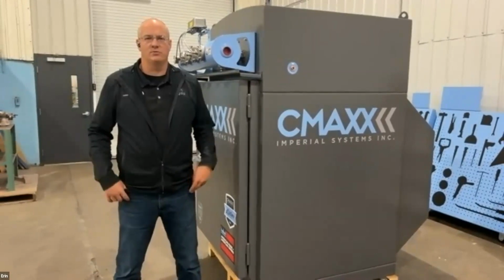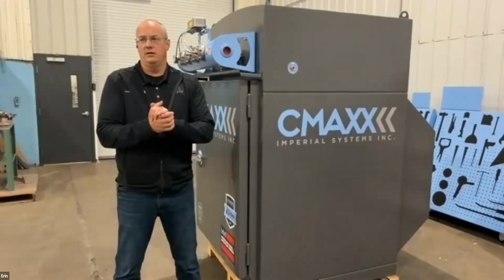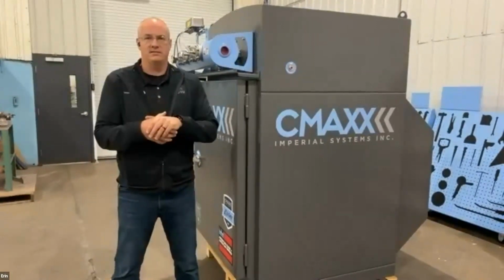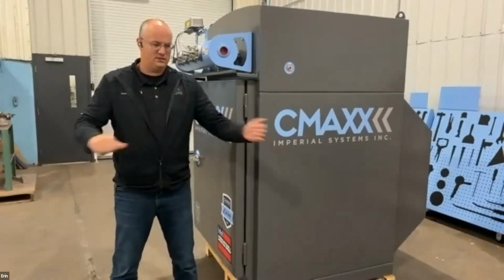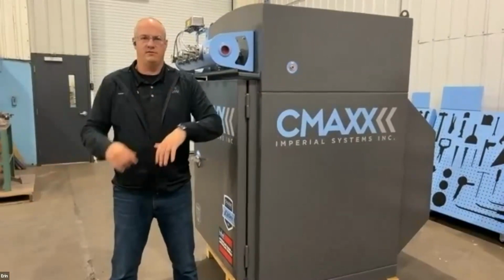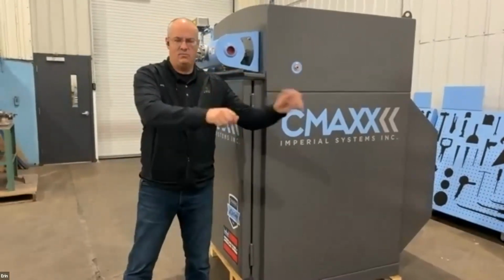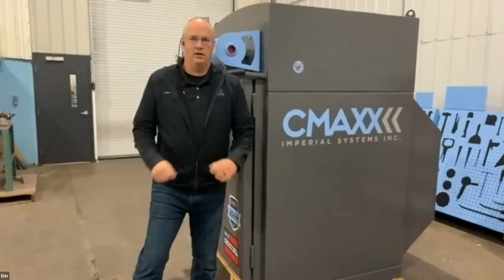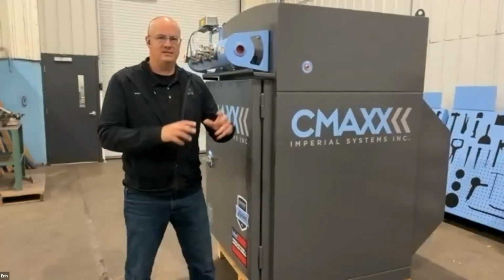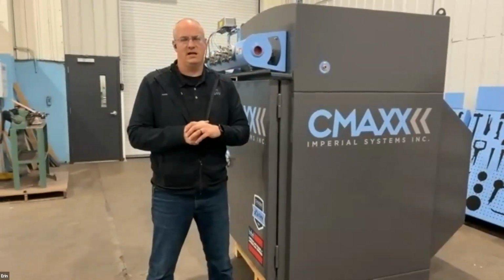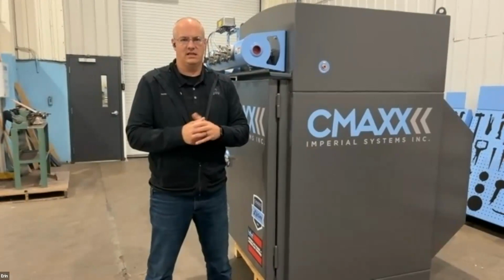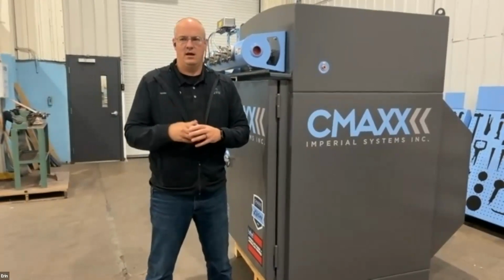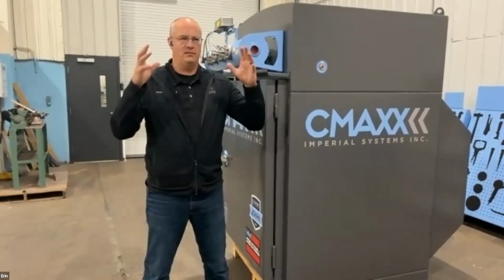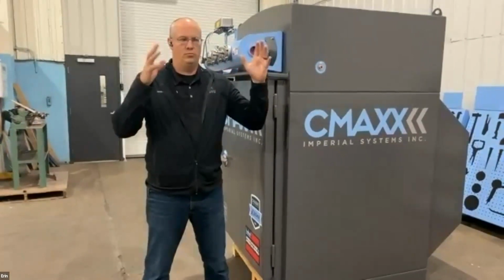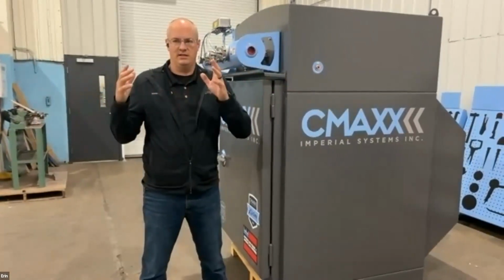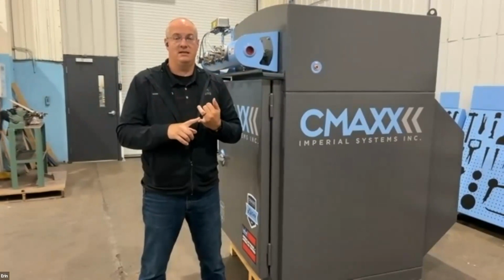A lot of the times when I'll see that is in maybe a knife shop, places that build knives, because they'll have the dust collector where they're grinding the knife, and they have the same one where they're working a handle, or using a resin to shape that. So I've talked to people in knife facilities. That's just one that came to the top of my head.